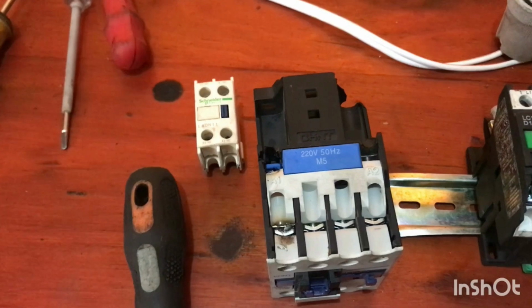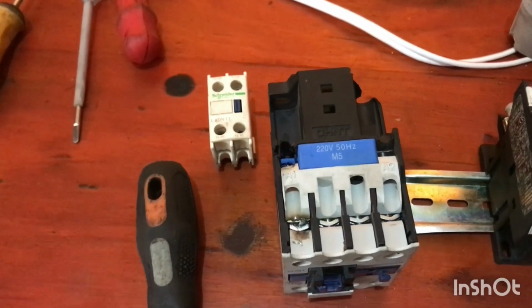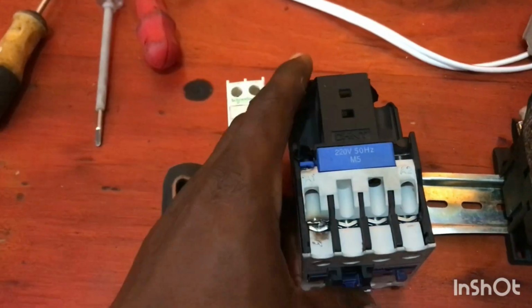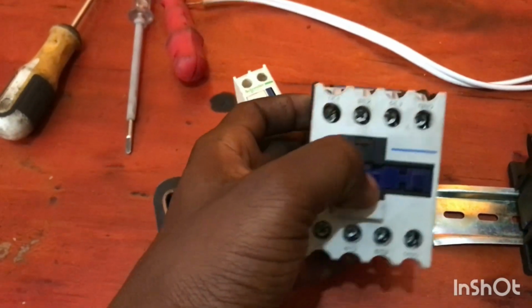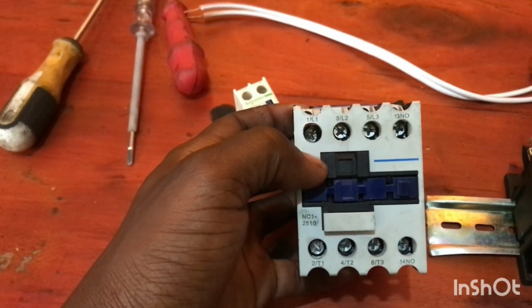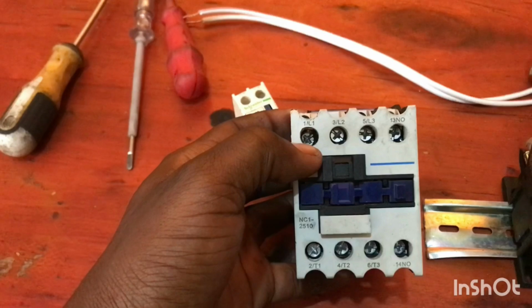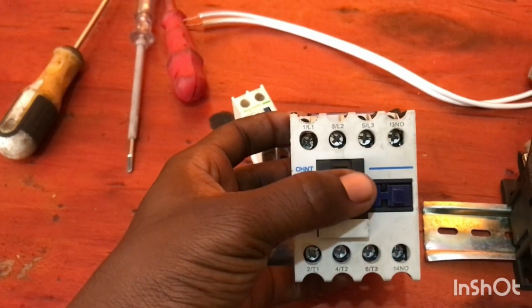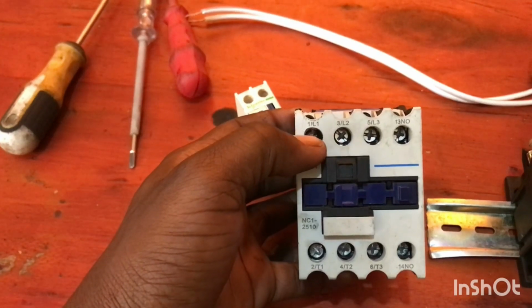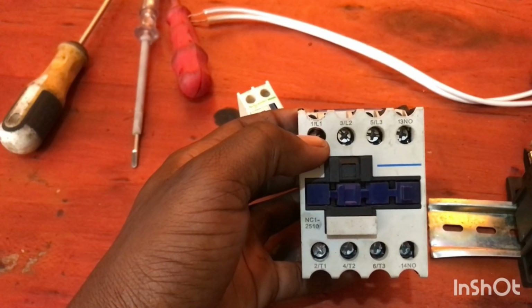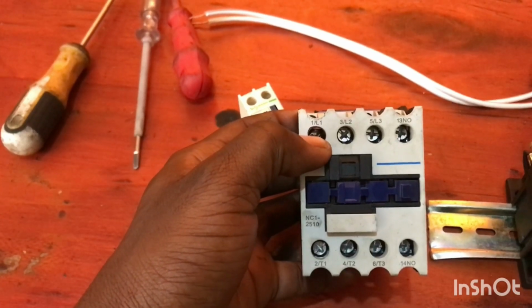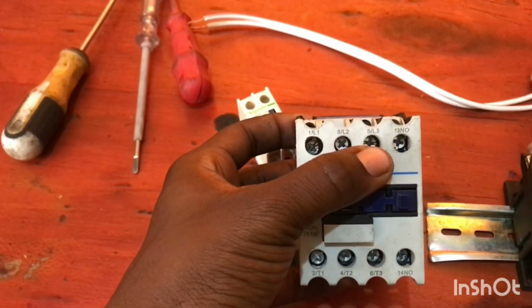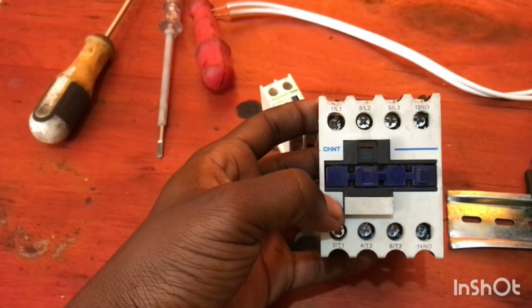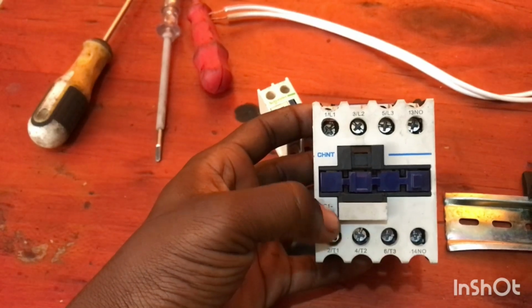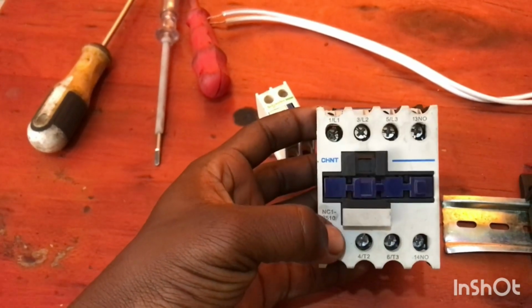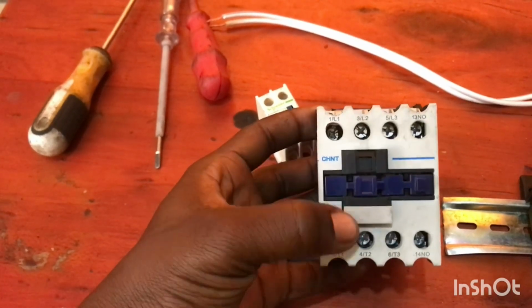So when you connect your A1 and A2, live and neutral, this contactor gets energized, or the electromagnetic relays which are inside get excited, making these points here, the L1, connect with the T1 which is down here. So when they get energized, if there is current at L1, current will also be there at T1, meaning the normally open will close, then the normally closed will open. So power goes from point A to point B when this contactor is energized.